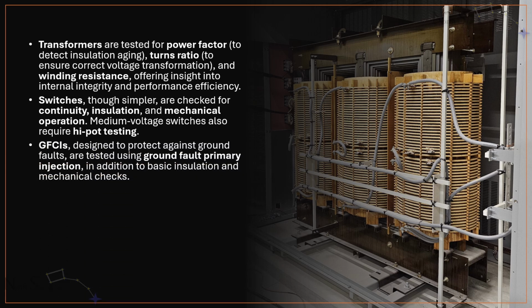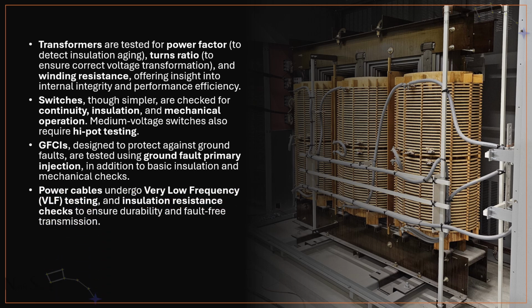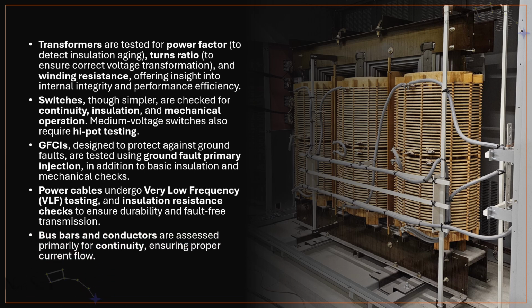GFCIs, designed to protect against ground faults, are tested using ground fault primary injection, in addition to basic insulation and mechanical checks. Power cables undergo very low frequency or VLF testing and insulation resistance checks to ensure durability and fault-free transmission. Busbars and conductors are assessed primarily for continuity, ensuring proper current flow. Each of these evaluations plays a role in a broader, condition-based maintenance strategy.